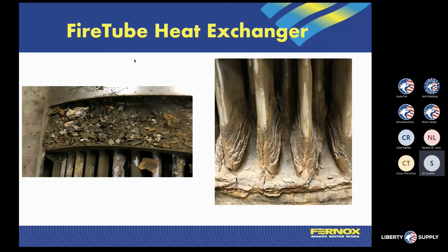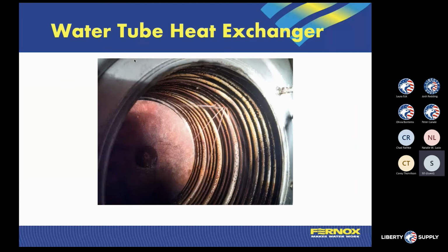So at this point, we're trying to circumvent that by pushing through that. So it takes more energy. Obviously, as the burner heats from the inner side of that tube, you're going to have more weak points because now we're going to be overheating these products where they normally would be transferring that energy into your fluid from that standpoint. So these are byproducts of that.